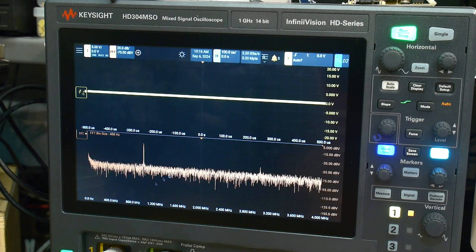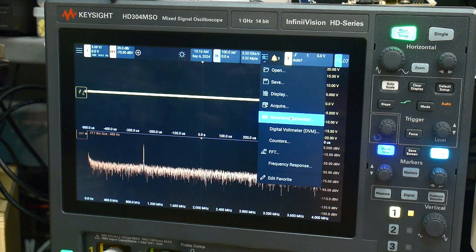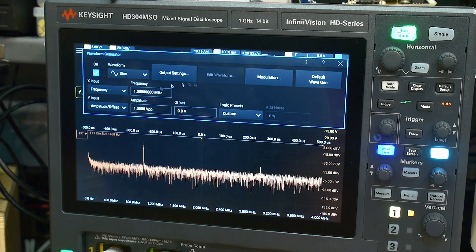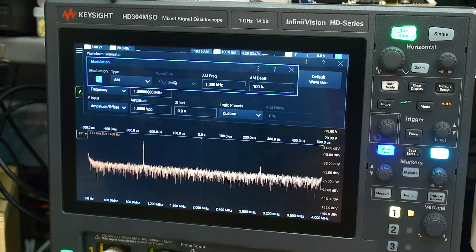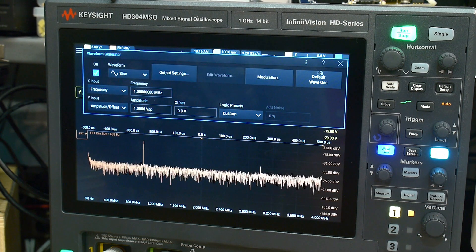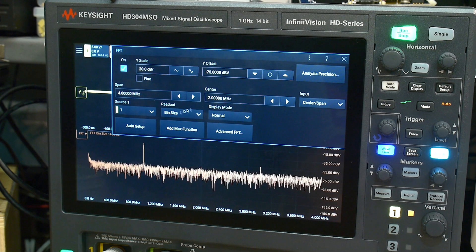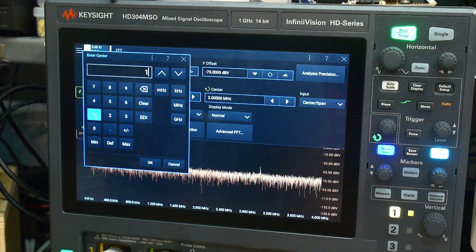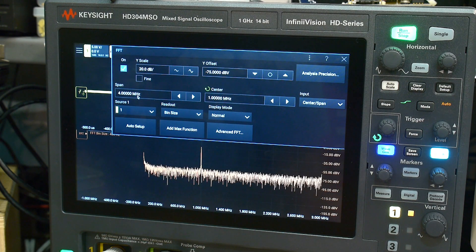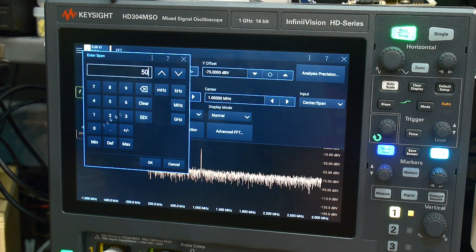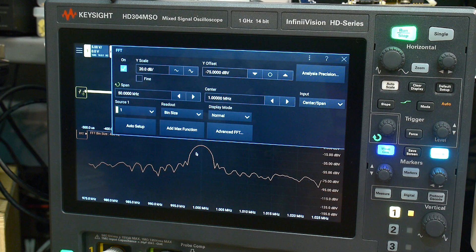What we have going on here is a wave generator. Our waveform generator is going to be set to 1 megahertz with a modulation of 1 kilohertz, 100% modulation depth. We want the center at 1 megahertz, and now we're in the center. We want the span — let's start at 50 kilohertz. There we go, but now we need more resolution bandwidth.